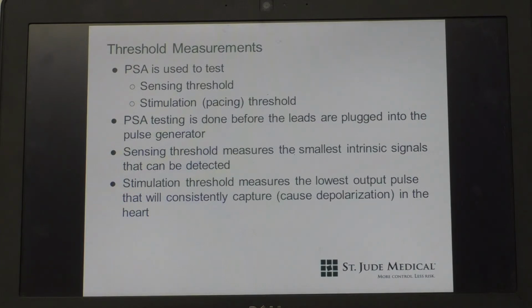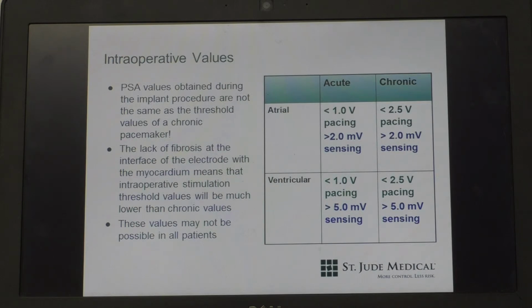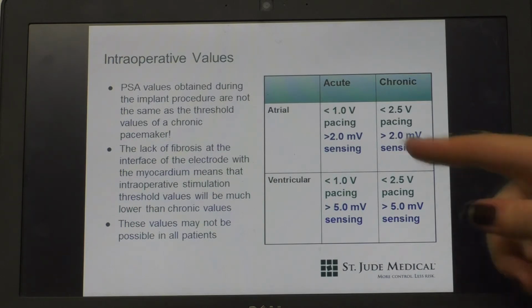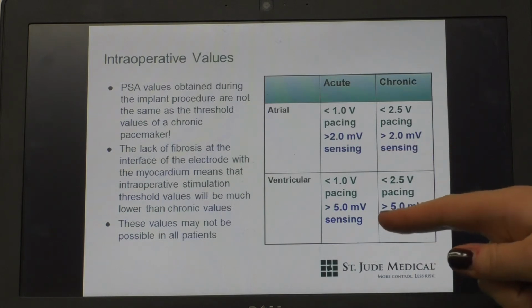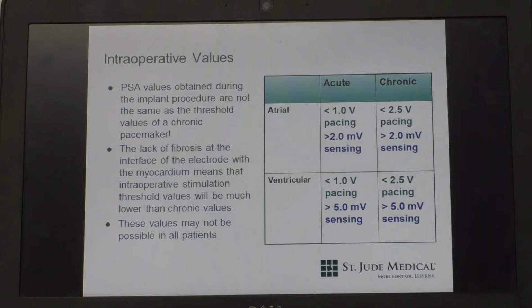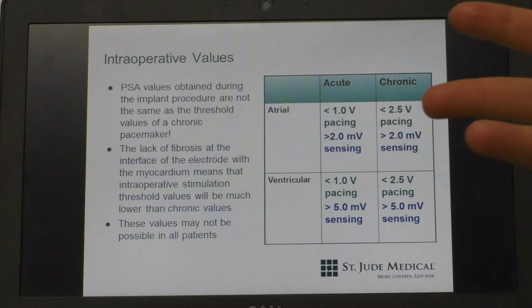So in textbook, you want thresholds under 1.0 volts, and you want greater than 2 millivolts sensing P waves, greater than 5 millivolts sensing R waves, and then less than 1 volt at 0.5 milliseconds capture threshold. If it's a difficult case, or say the patient has a lot of scar, I have accepted higher, but ideally under 1 is better. And typically the next day it's either the same or even goes down, because the pacing leads have steroids at the tip. So when you first screw in the lead, or even a passive lead, you kind of bite into the tissue and it causes an acute inflammation, and that can elevate the threshold temporarily 1 to 2 days. So to combat that, they started adding steroids 10 years ago to the leads, and it helps a lot. But even with the steroids, the next day the threshold can come down.